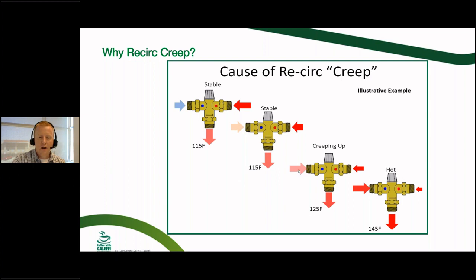But sooner or later, that recirc is going to start coming up in temperature a little bit, and you're going to notice the mixing valve is going to want to try and clamp down on that hot inlet, but it can't. It physically can't shut it down all the way, and you'll notice that your mixed outlet's going to start coming up in temperature. And again, as that temperature starts coming up, the mixing valve tries to clamp that hot inlet down as much as possible, but it can only do so much.